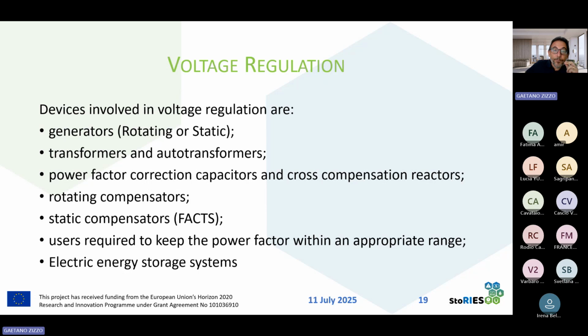So the devices involved in voltage regulation are usually generators that are rotating or static, transformers and autotransformers, power factor correction capacitors and shunt compensation reactors, rotating compensators, static compensators, the so-called FACTS, users, semi-users of the system that are required to keep their power factor within an appropriate range, usually between 0.95 and minus 0.95, and then electrical energy storage systems. In reality, this last point can be included both in the case of FACTS and in the case of generators, since if we remember the definition of storage systems given by the Italian technical rules, they are systems that are considered of the same kind of power generators.